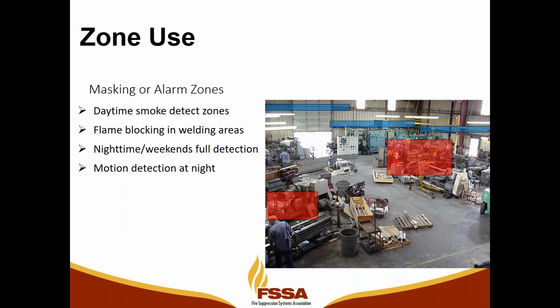These zones can be set on a schedule, so nights and weekends, the system is wide open for alarm anywhere in the field of view for flame or smoke. You can also set up a motion detect zone for additional security. One of the relays on the camera can be motion. The other relay, the alarm relay, can be smoke and flame.